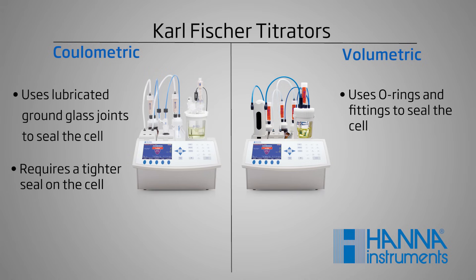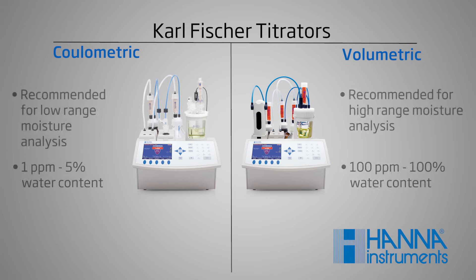So what does all this mean for you? At Hanna we usually recommend volumetric titrators for high range moisture between 100 parts per million to 100% water content. For lower ranges from 1 part per million to 5%, the coulometric titrator is best suited for the job.